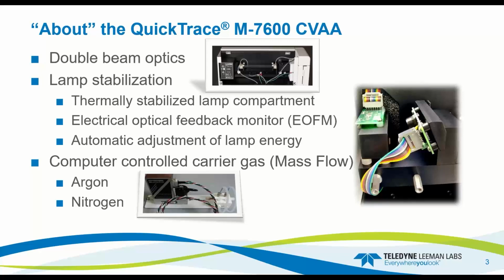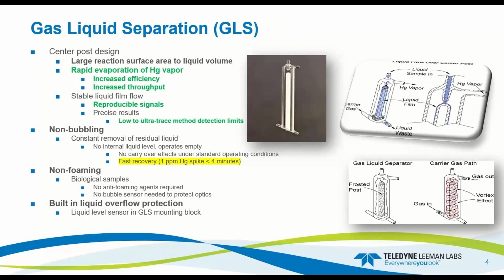The carrier gas is controlled by a mass flow controller. You can either use argon or nitrogen. So it's very stable gas flow with the system. Liquid separation, gas liquid separator. So it's a center post design. Large reaction surface area to the small liquid volume. That gives us rapid evaporation of the mercury into the gas stream. Increased efficiency increases throughput. That's a stable liquid film flow. That is going to give us reproducible signals. And with reproducible signals and the stability of everything, now we have precise results. So low to ultra trace method detection limits.